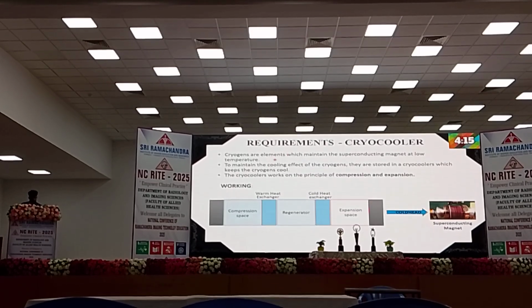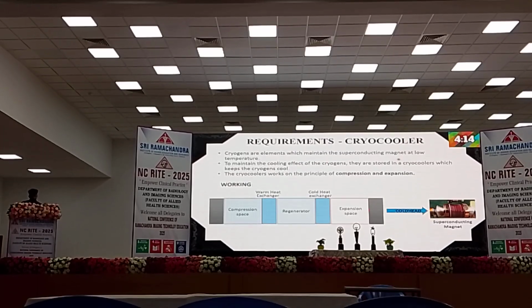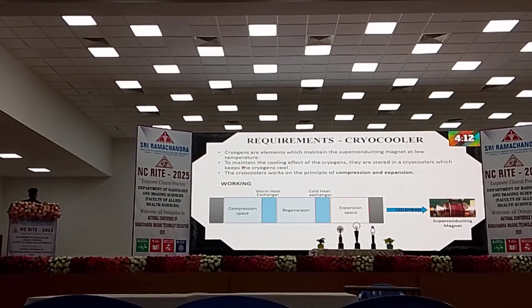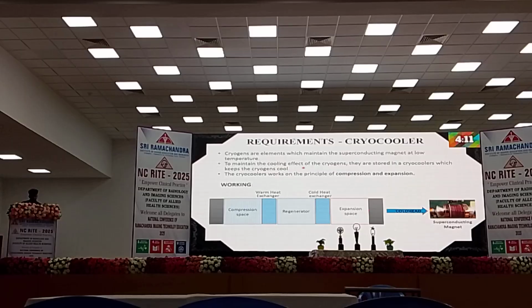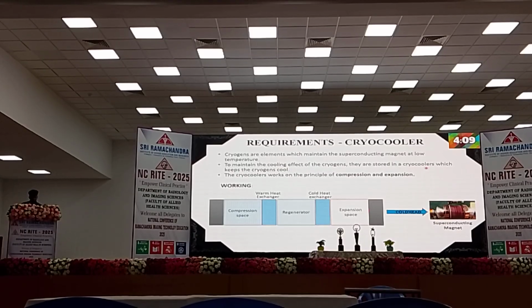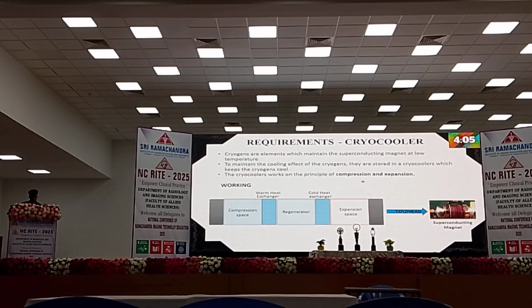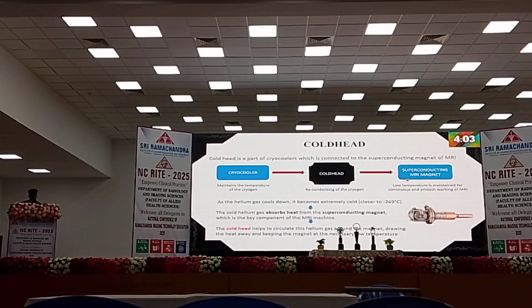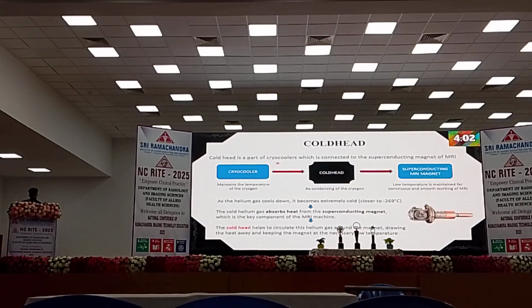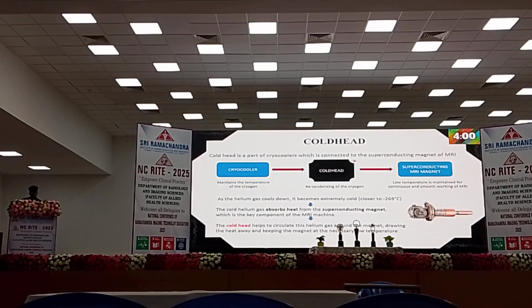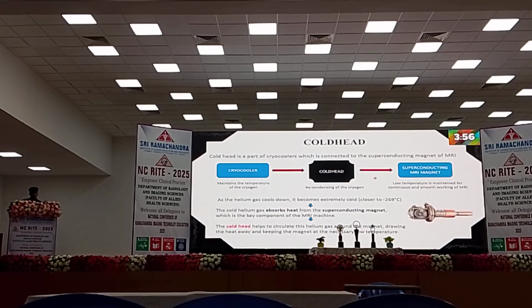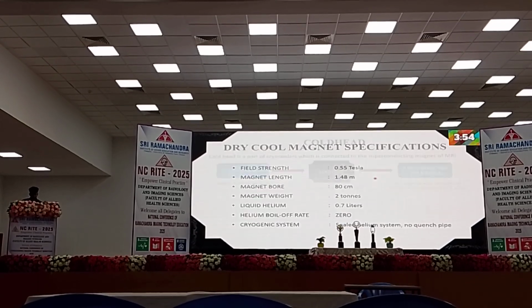Cryogens are elements which maintain the superconducting magnet at low temperature. To maintain the cooling effect of cryogens, they are stored in the cryocooler which keeps the cryogen cool. The cryocooler works on the principle of compression and expansion. A cold head is the part of the cryocooler which is connected to the superconducting magnet of the MRI. The cold head is used to circulate the helium in and around the magnet.